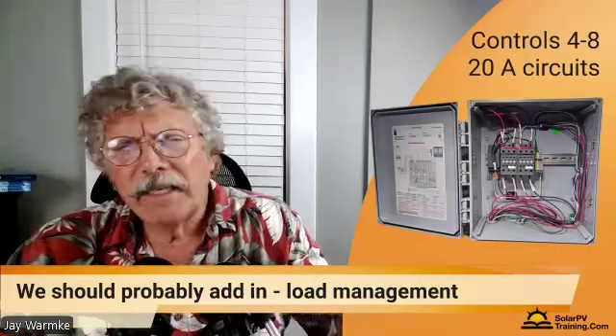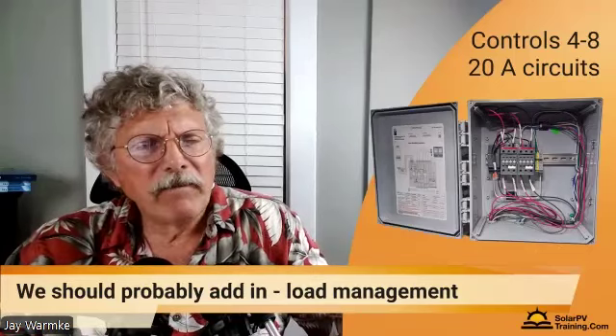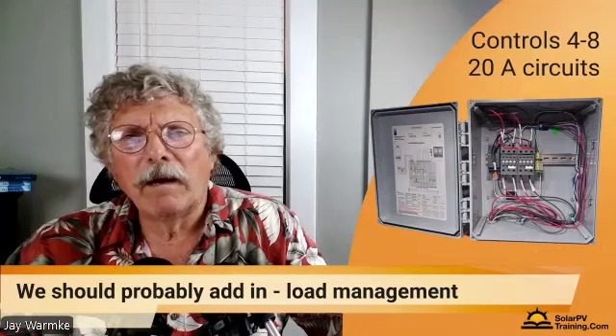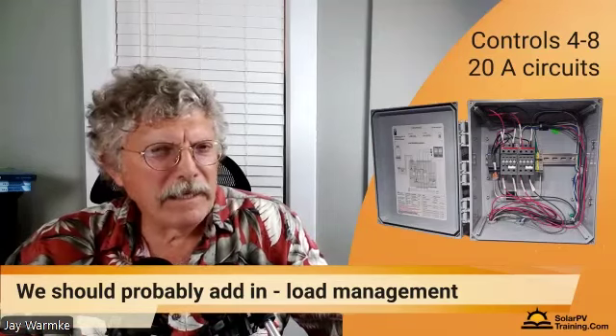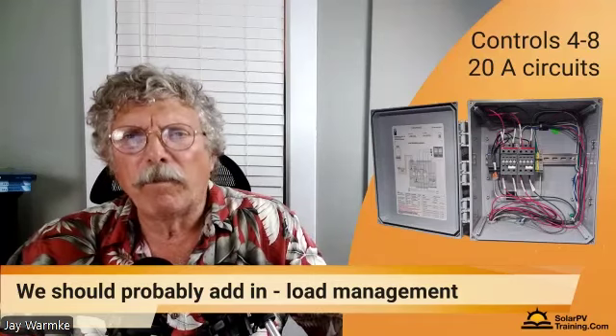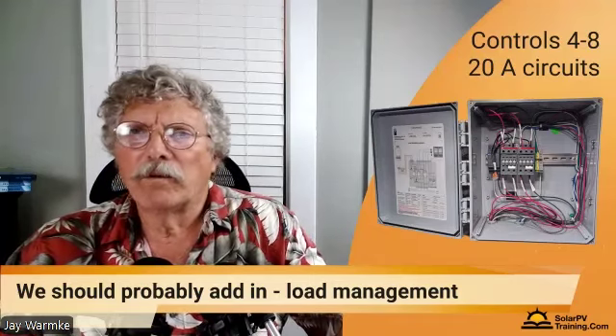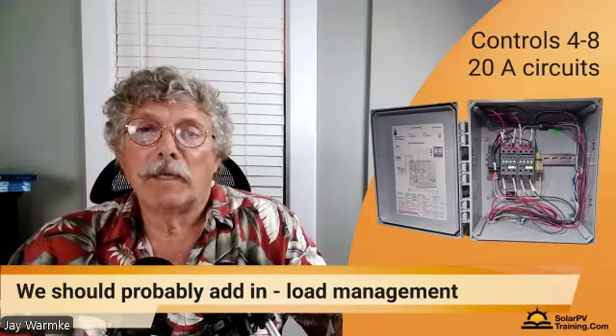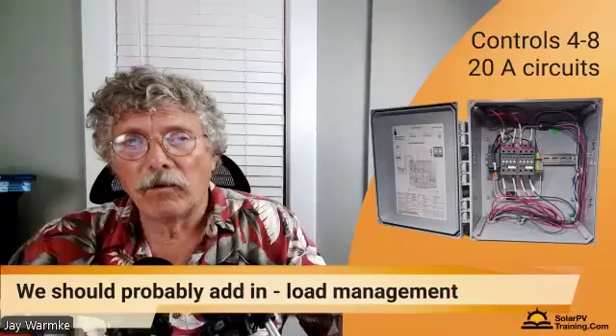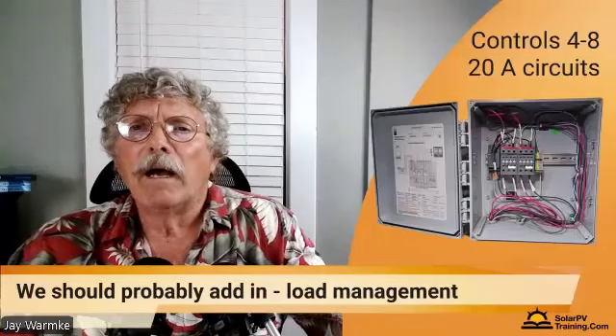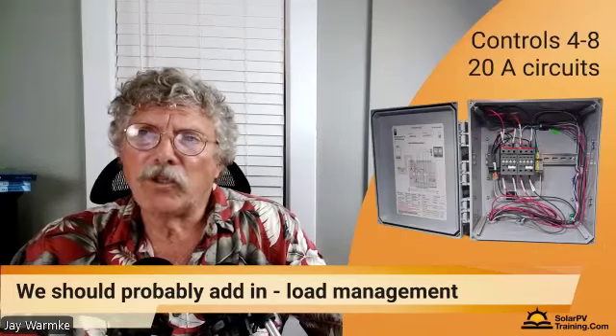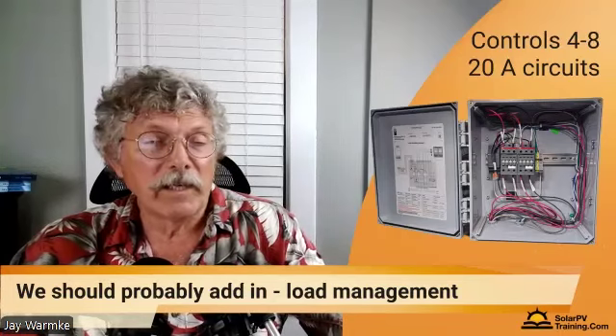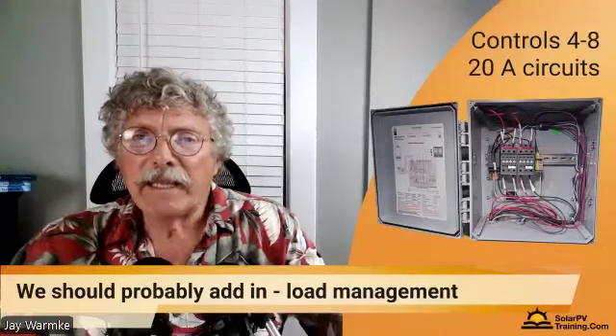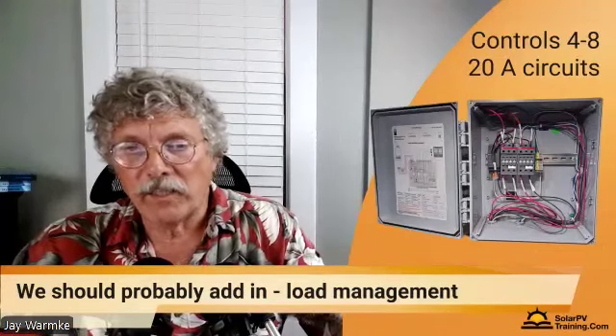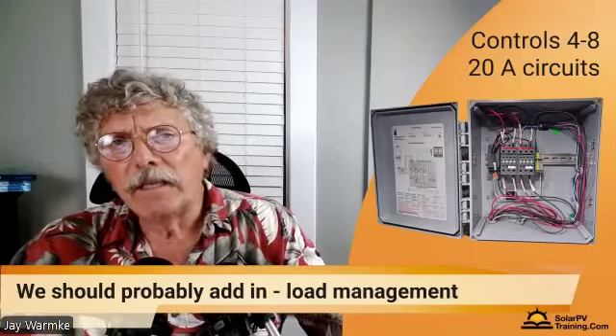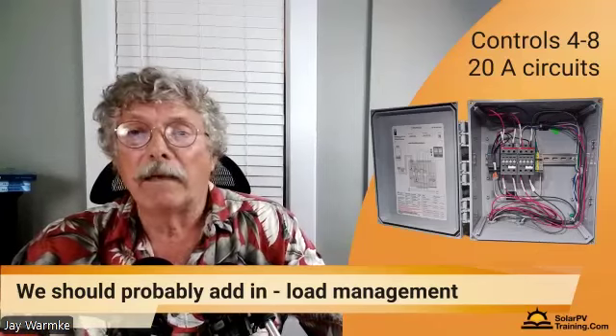And I don't know why they did this in double pole. Maybe because everything's 240 volts. So, but you're not typically going to have 240 volt appliances as part of your critical load backup. If you had a huge system, maybe, and probably the only one's going to be your air conditioner. But in this case, you're going to be operating 2 120 volt circuits, and just splitting these 240 double pole breakers into 2 separate circuits, and they'll feed into your backup load panel.